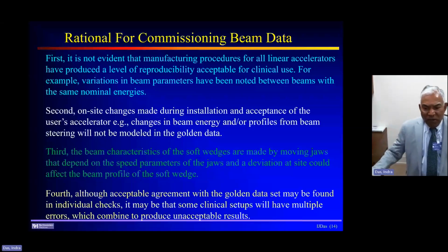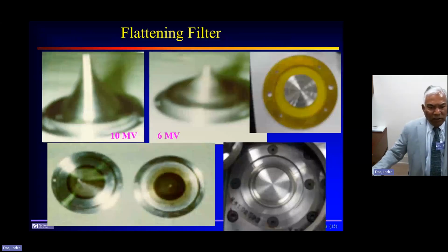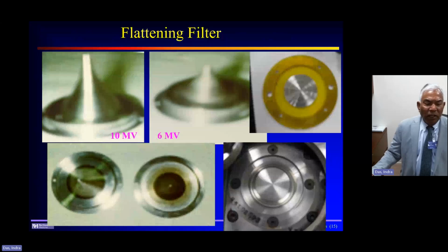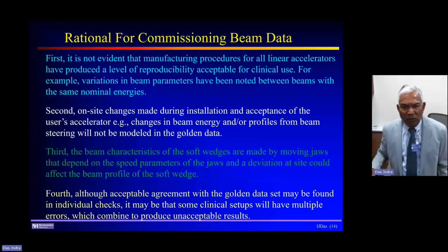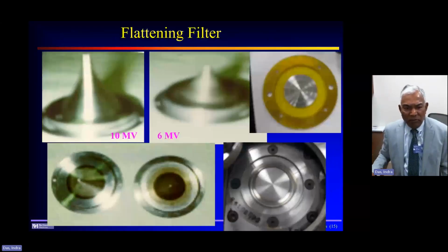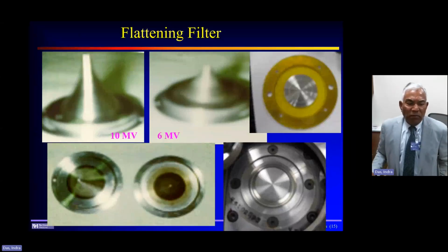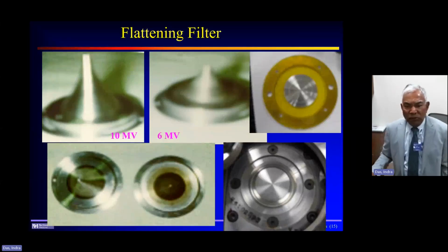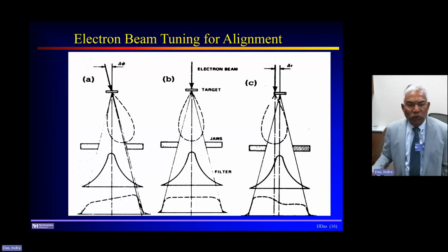And agreement between the golden data sets, it may be in a certain time that you might agree. And so these are some rationale why you must commission the beam data. The other thing for photon beam, that we use the flattening filter, and this is a typical flattening filter, but that's not what I want to show you.